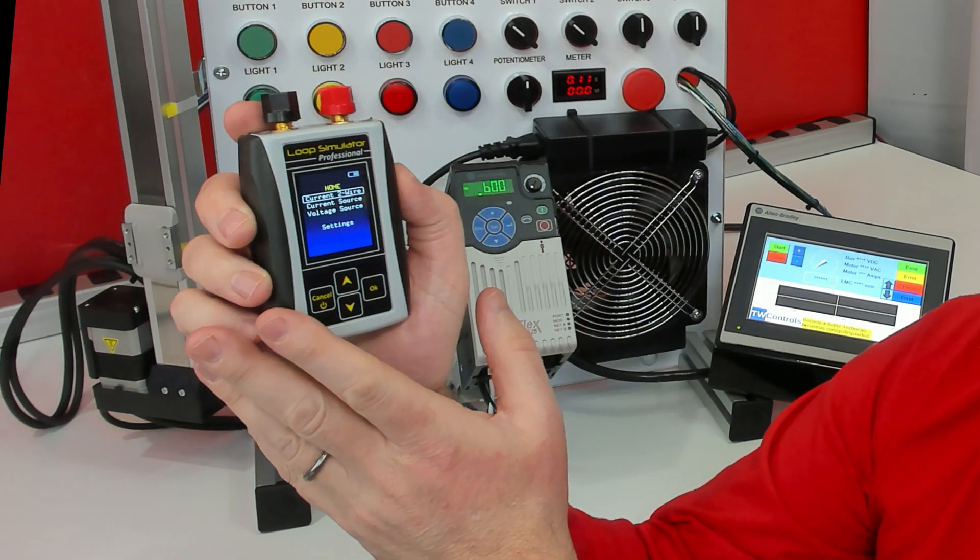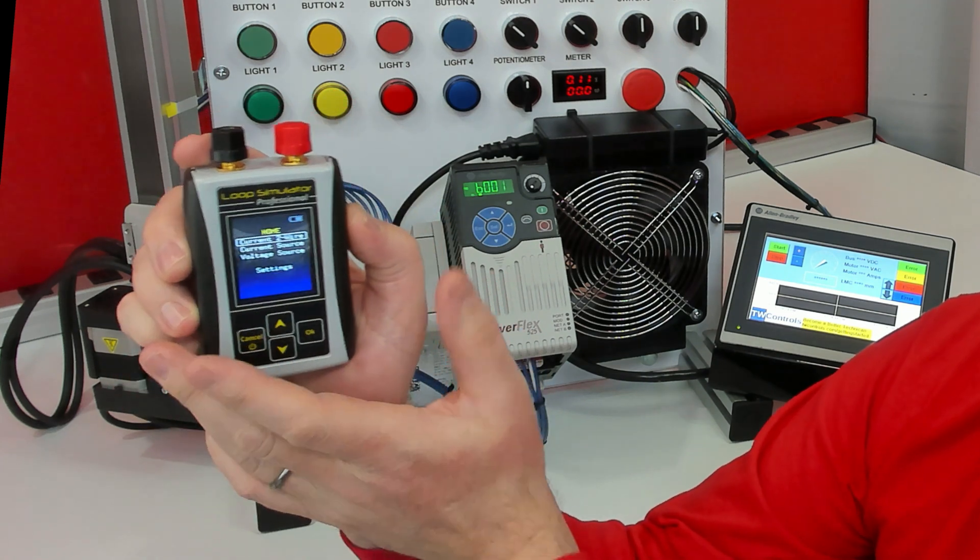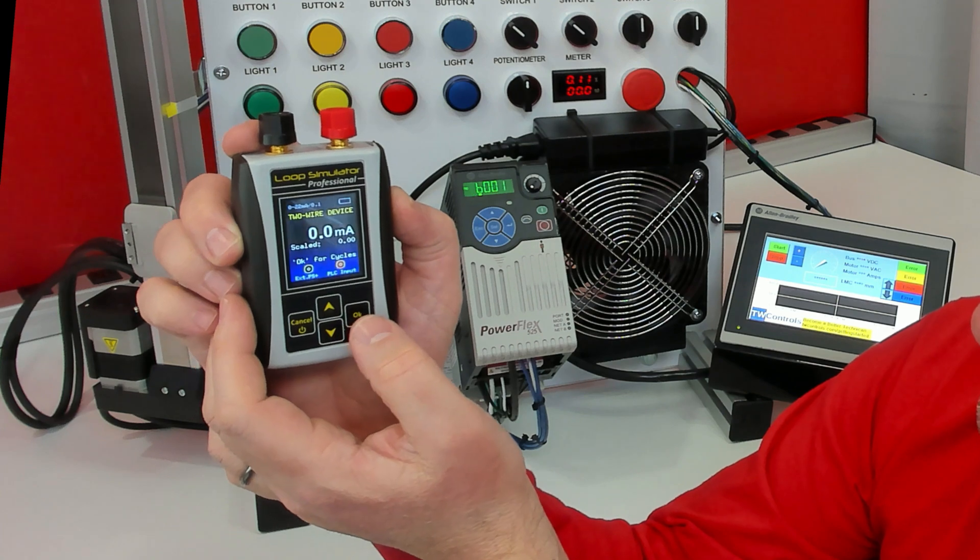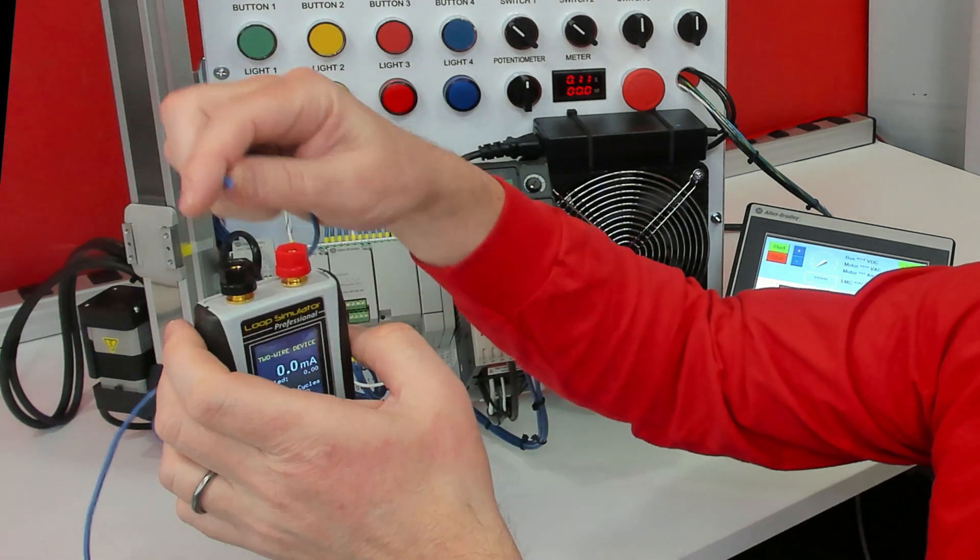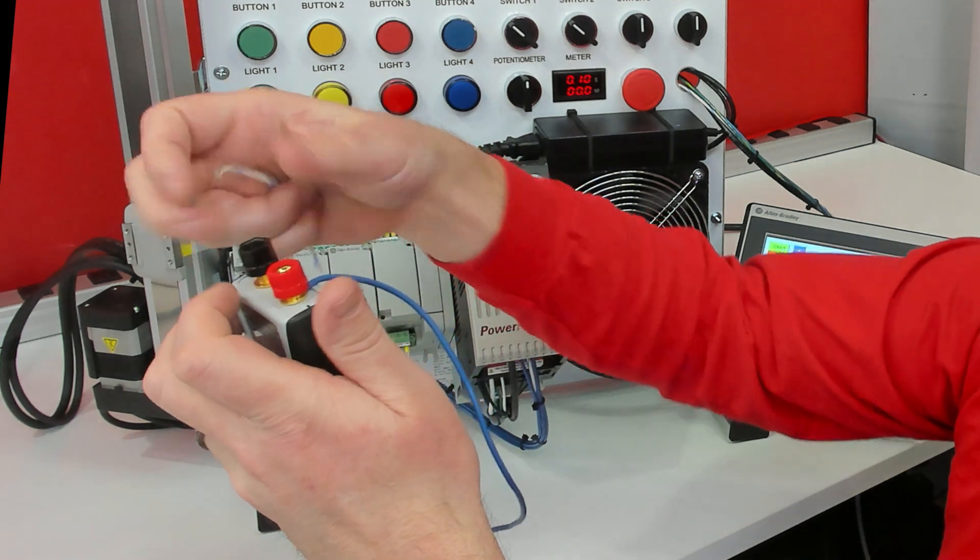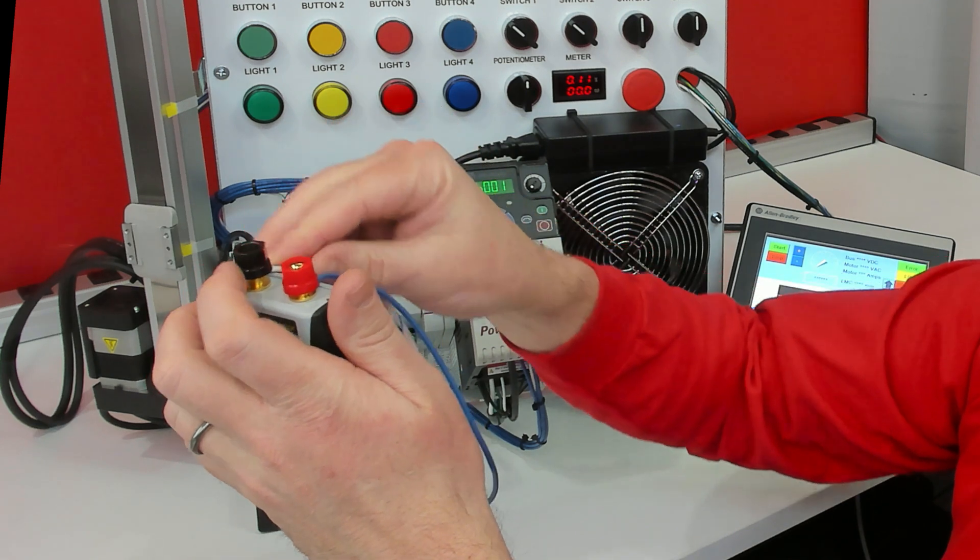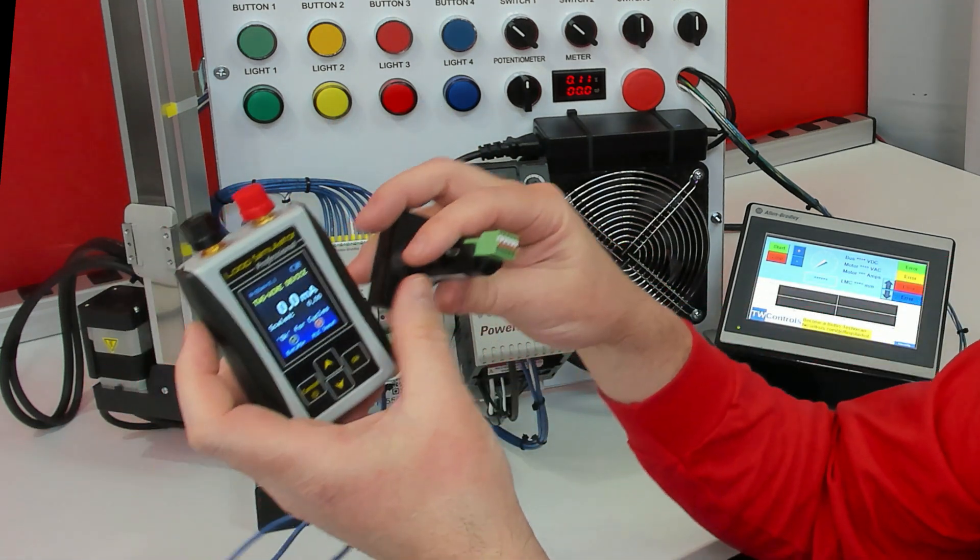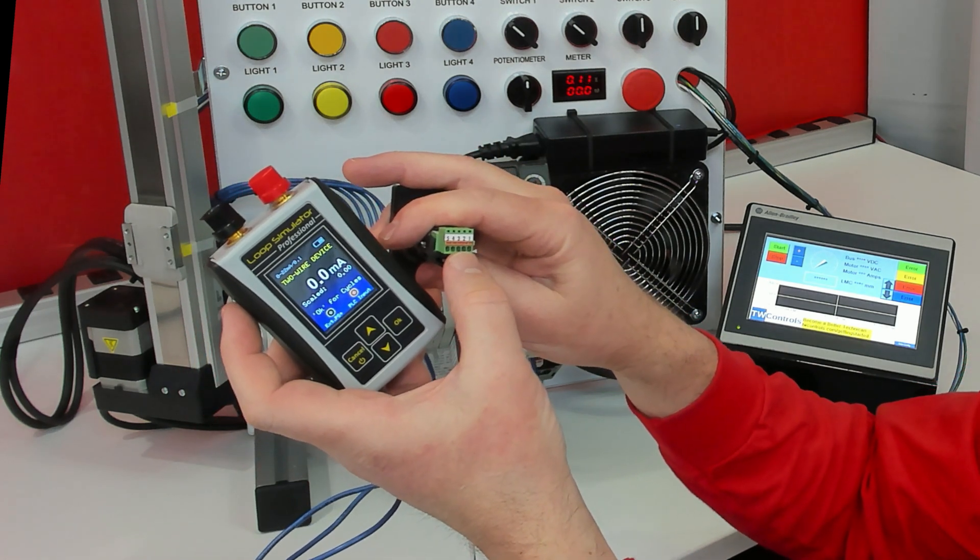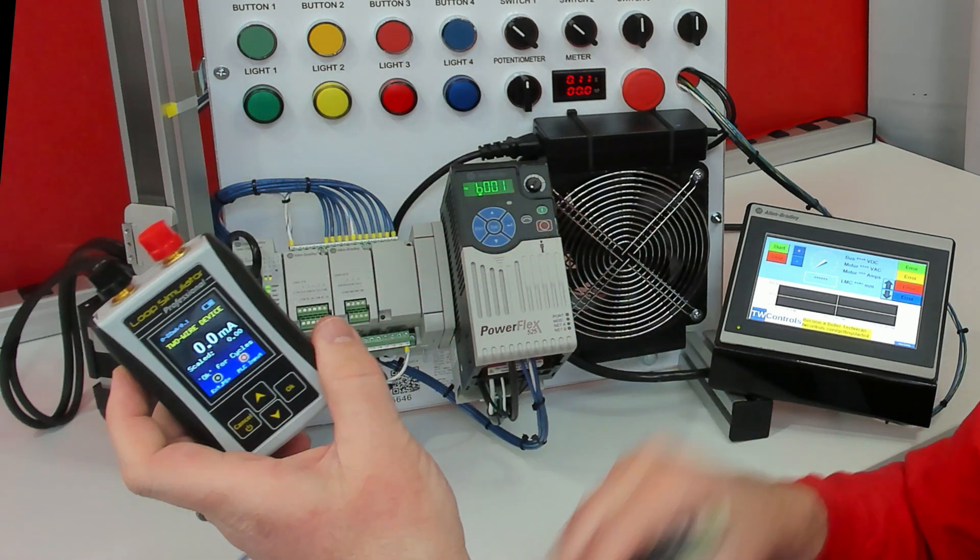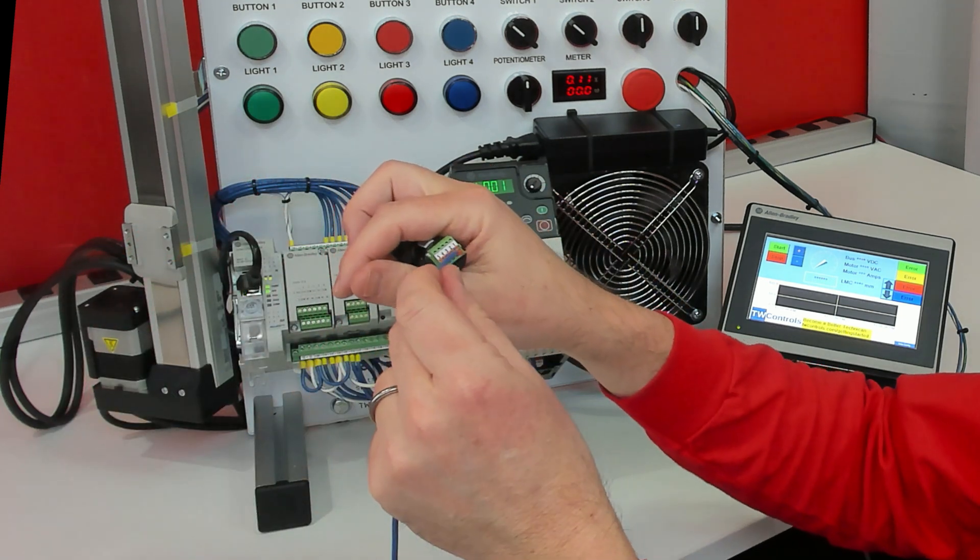Now let's take our analog simulator. And let's just start with current two wire. So I'm going to select two wire. And I am going to put the blue wire on my red post. And then I'm going to put my white wire under the black post. And on my meter, my positive milliamp is terminal one, my negative is terminal two. So I'll put my blue wire into terminal one.